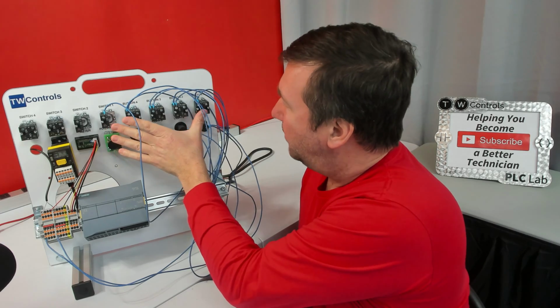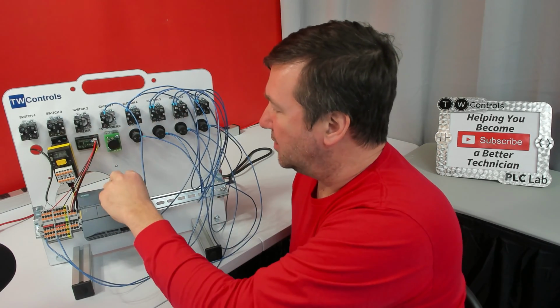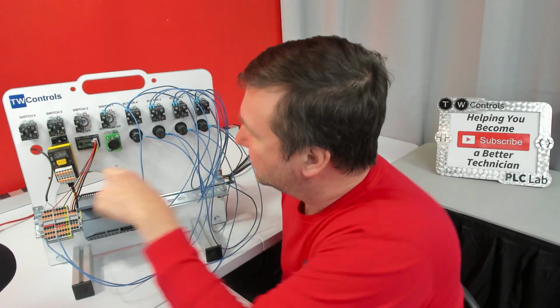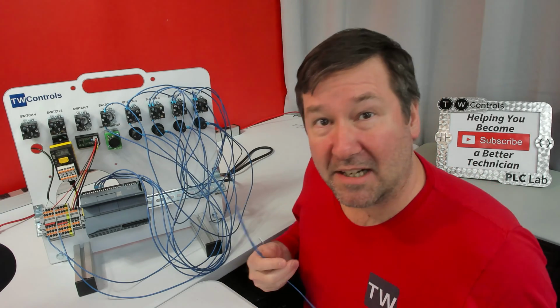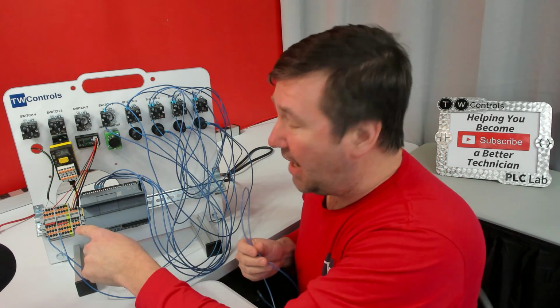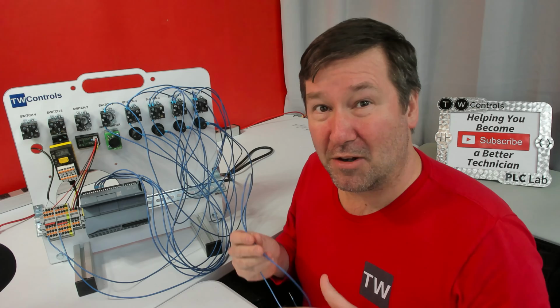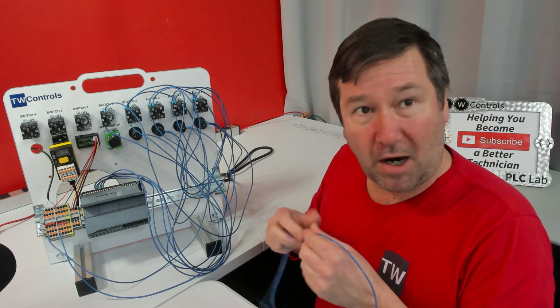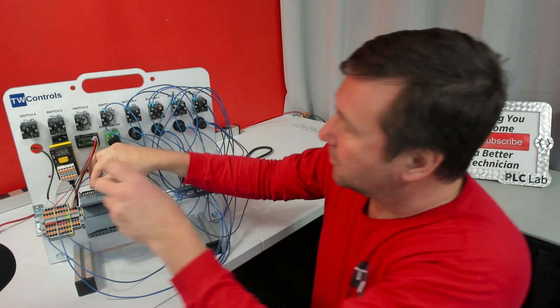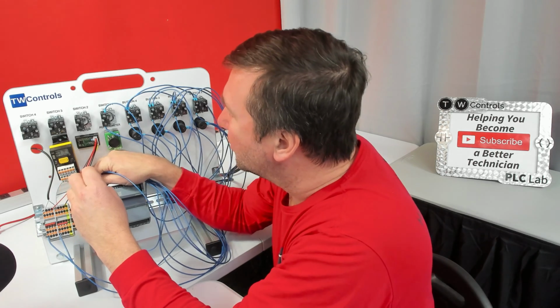So let's go ahead and connect the bottom of our buttons and switch 1 to our inputs. And those are these top terminals here. Now we need to connect 1M to the minus of our power supply. And this is by far the most often overlooked wire because that is what's going to complete our circuit to make our inputs turn on.